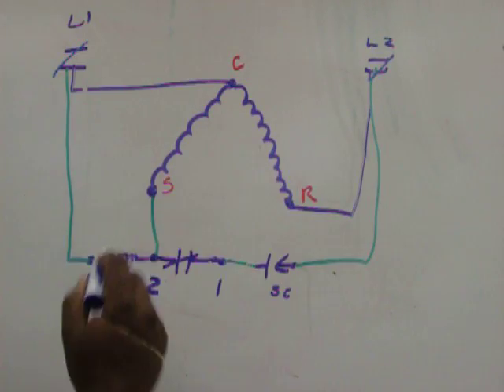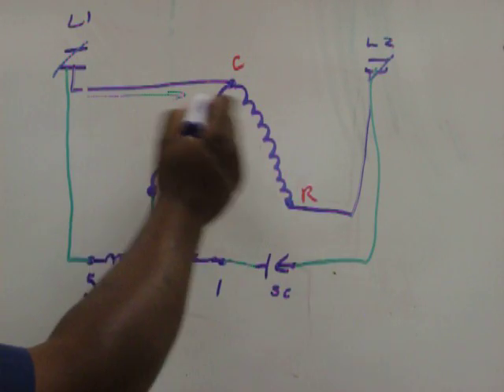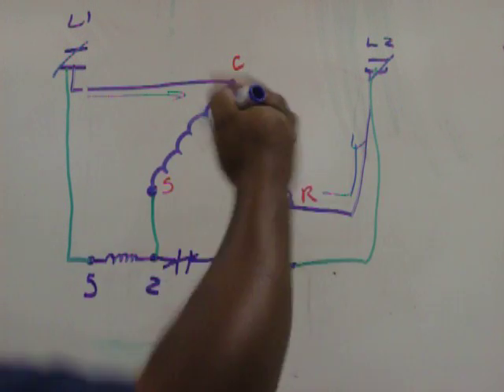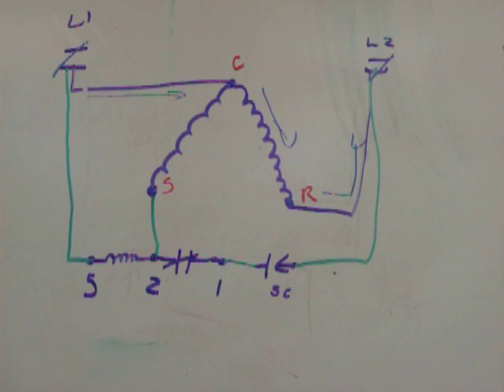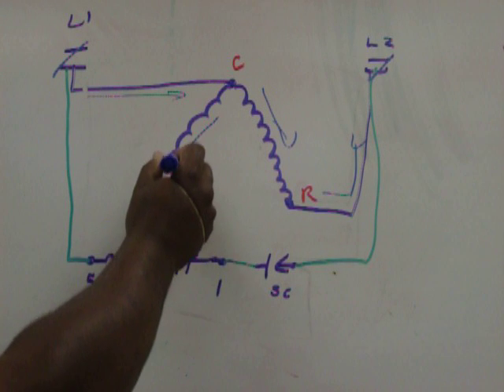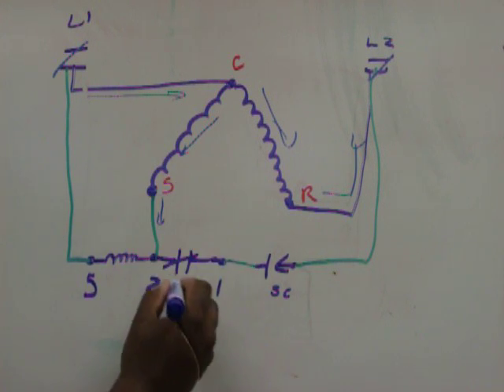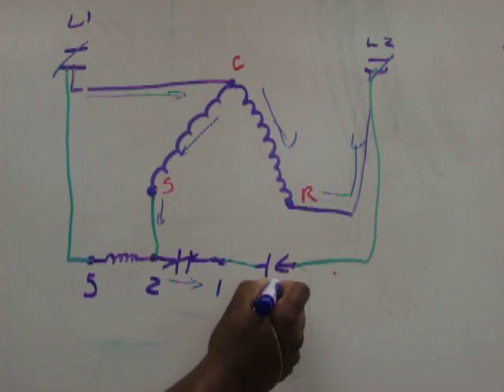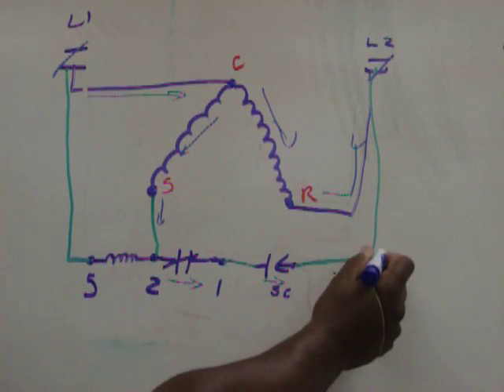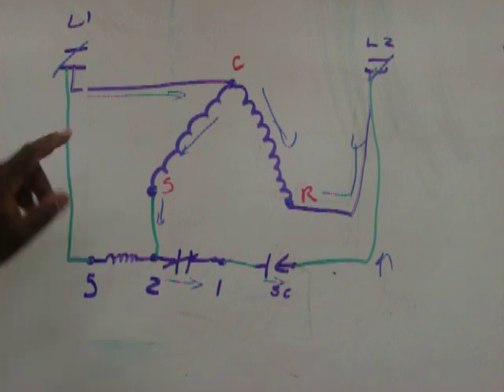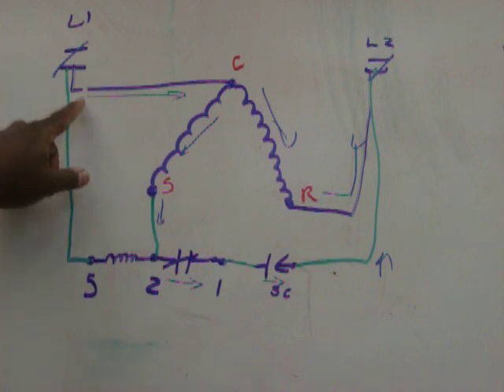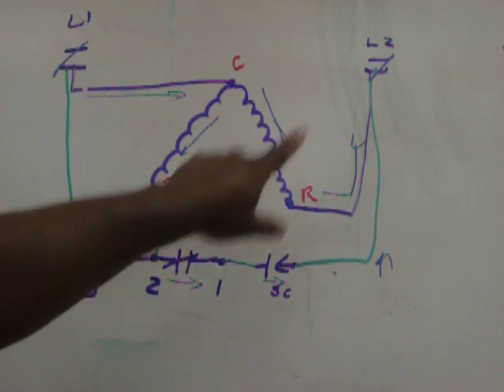Contactor closes. Power goes through here. And initially, we have a circuit through the run winding. So run winding is energized on startup. We also have a circuit that comes through your start winding. It goes through the normally closed set of contacts, through your start capacitor, and to the other side of power. We have to have a good understanding of electricity. You have to leave one side of power, go through your load, and go to the other side of power.